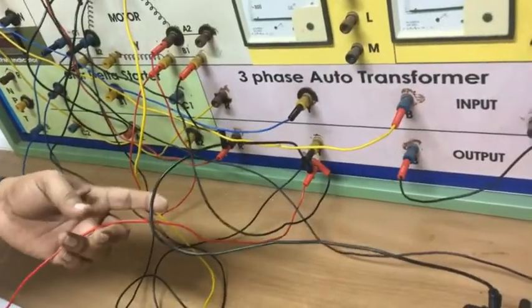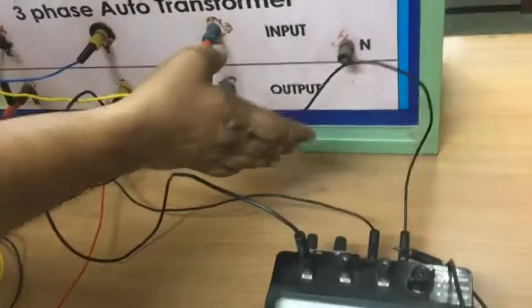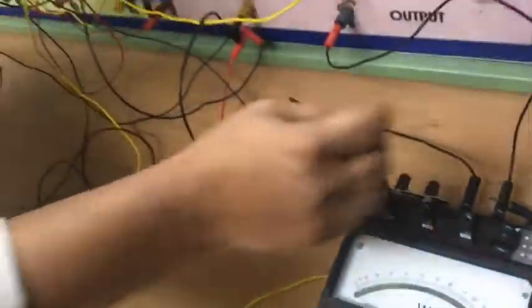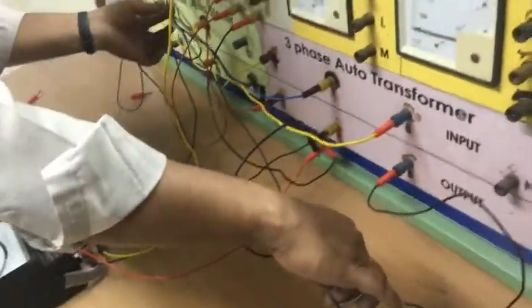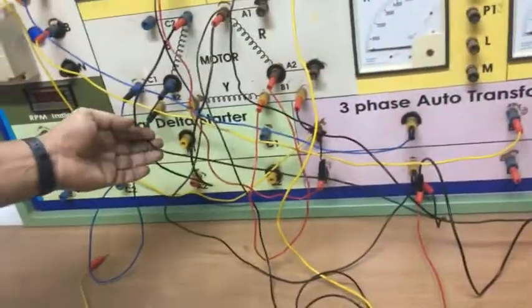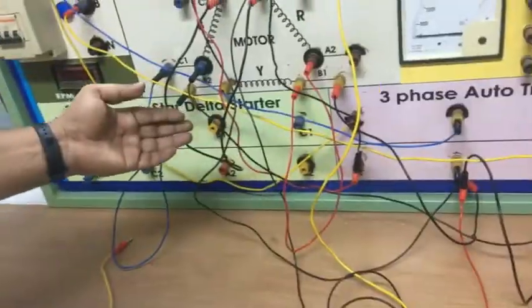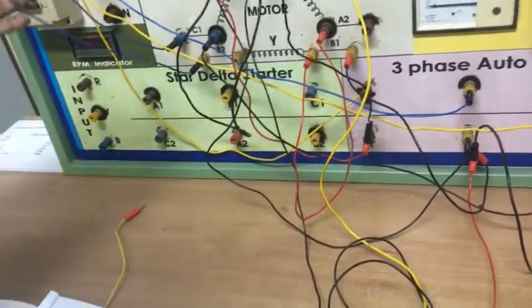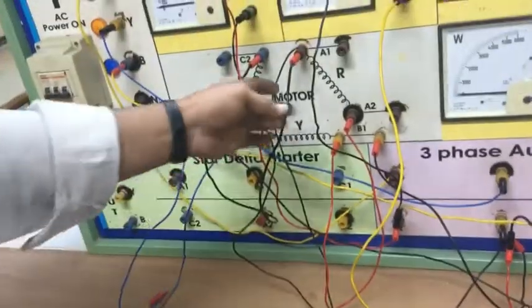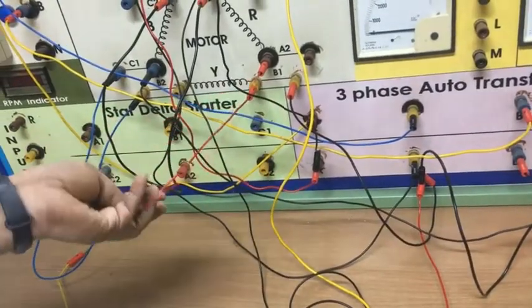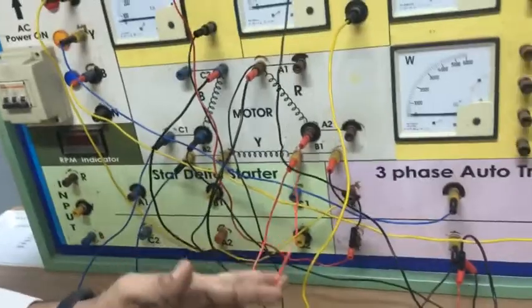Next, the other terminal, that is B phase, will be connected to wattmeter M. Again M and C are shorted. Next, from L we are connecting to another winding of the induction motor, that is B2. After connecting the terminals, short C1 B2, short A1 C2, and short B1 A2. So this is with respect to your no load connection.